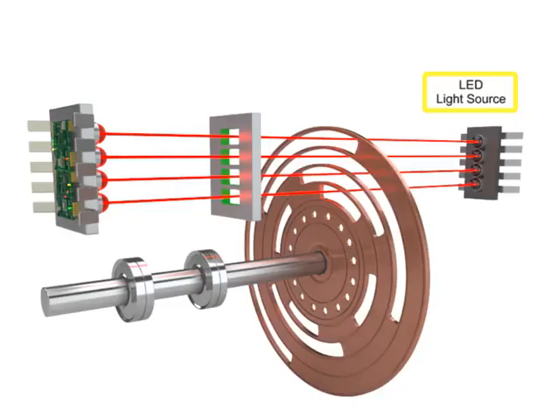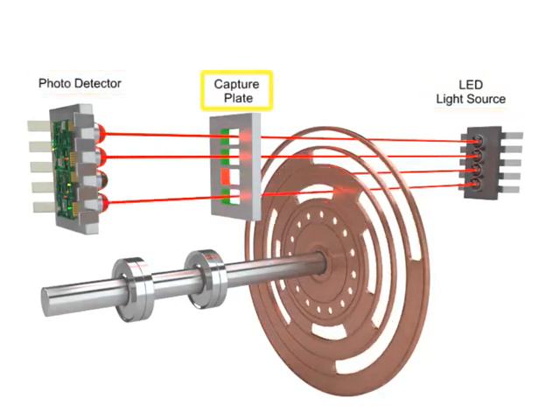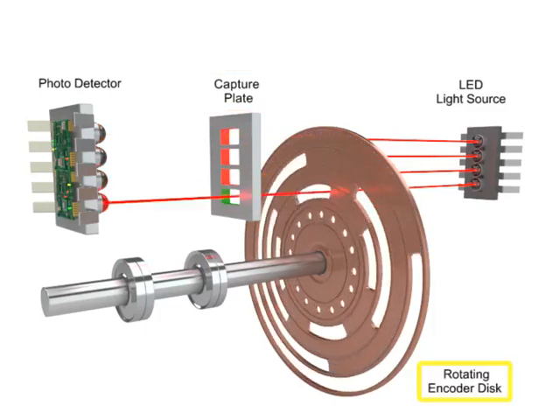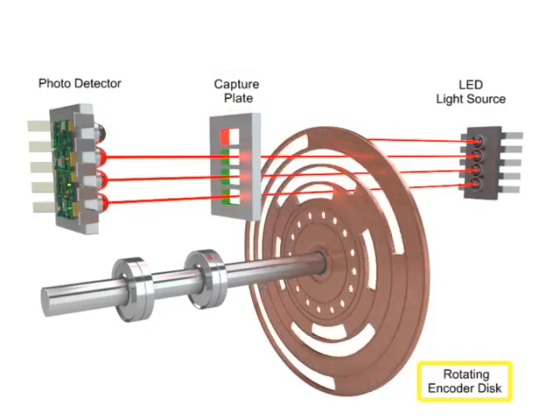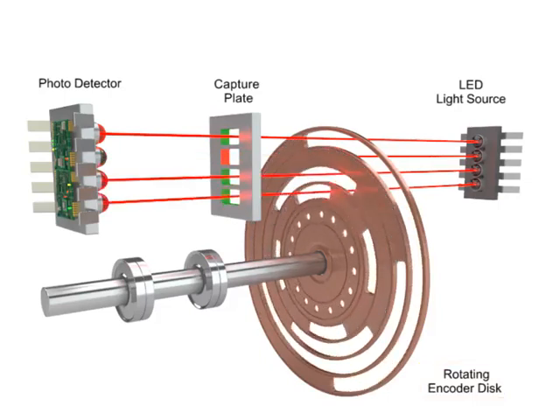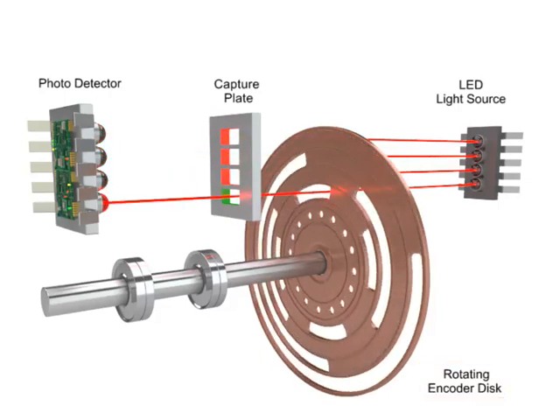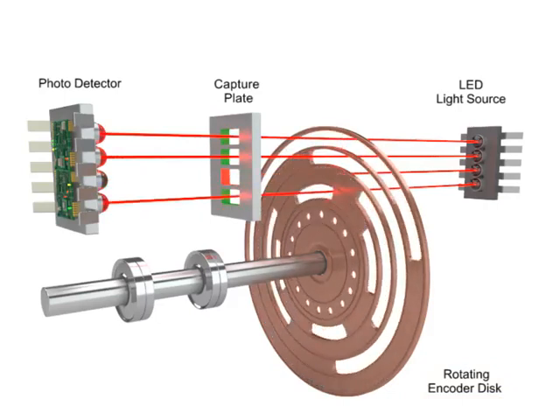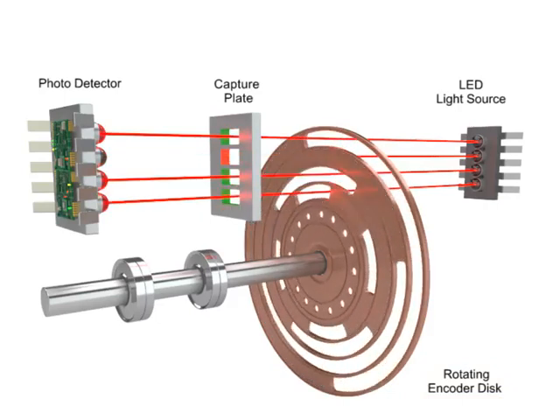A light source located on the opposite side of the photocells passes light through a capture plate. As the encoder disc rotates, light is either transmitted or blocked according to the pattern. The received light provides a four-bit word that indicates the position of the actuator or device the encoder is mounted to.